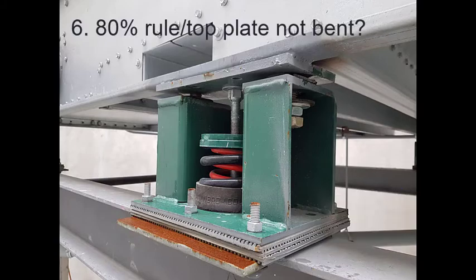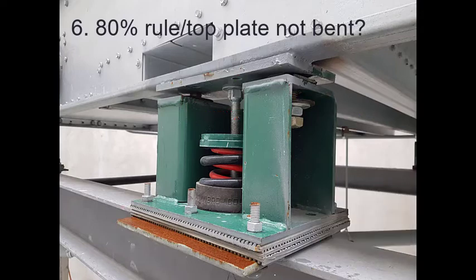Is the equipment supporting less than 80% of the top plate? Well, it's hard to say for sure. I didn't measure it. But it doesn't matter in this case, since the equipment load is primarily along the long axis center of the top plate. The missing description in the installation instructions' extra top plate requirement is that it really only applies when the load is perpendicular to the plate or if the equipment foot is smaller than the opening or distance between the side stanchions. In other situations where the equipment support is smaller than 80% of the top plate, as long as the top plate is not deformed and nothing else damaged, then it would be okay.